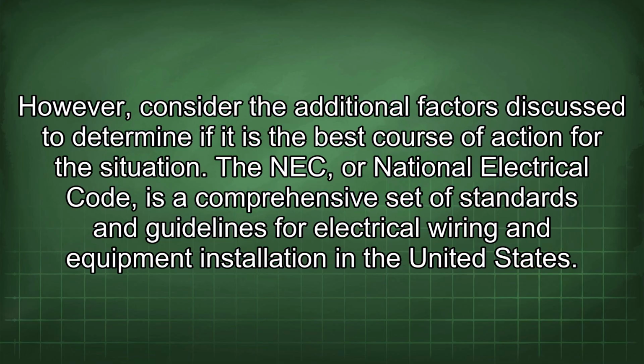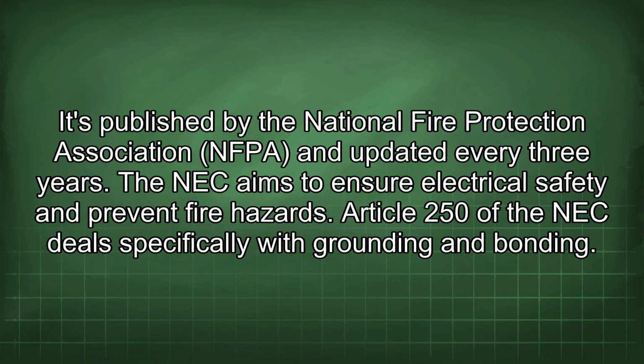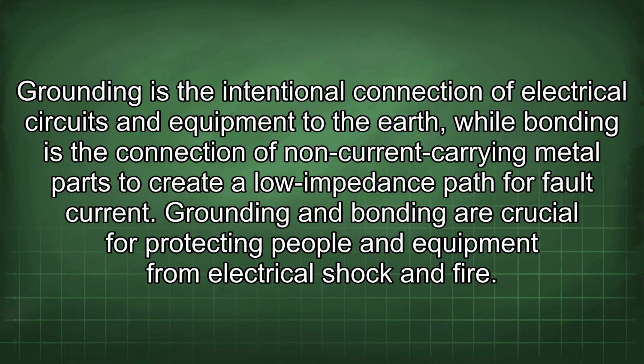The NEC, or National Electrical Code, is a comprehensive set of standards and guidelines for electrical wiring and equipment installation in the United States. It is published by the National Fire Protection Association (NFPA) and updated every 3 years. The NEC aims to ensure electrical safety and prevent fire hazards. Article 250 of the NEC deals specifically with grounding and bonding. Grounding is the intentional connection of electrical circuits and equipment to the earth, while bonding is the connection of non-current carrying metal parts to create a low impedance path for fault current.